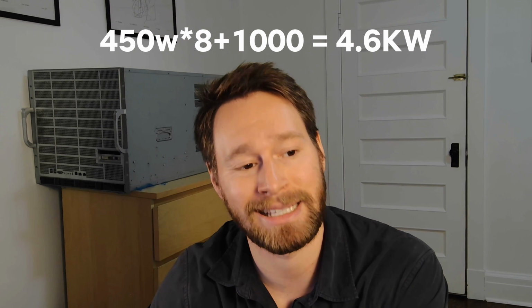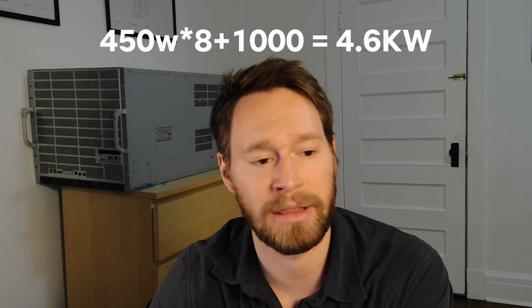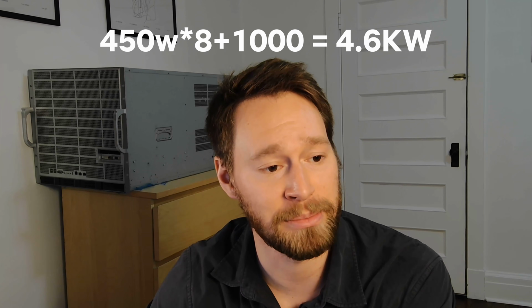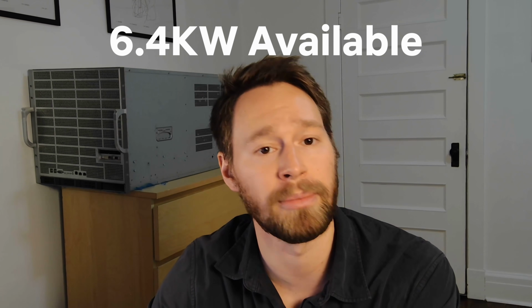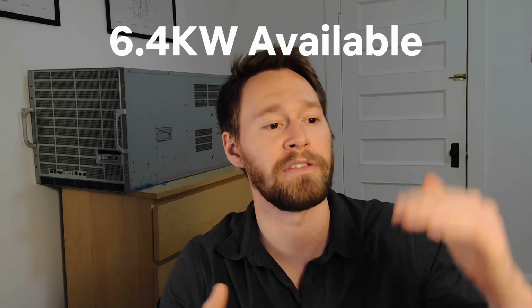For a 4090 server, the math is you need about 4.6 kilowatts to run it. I think that math was just TDP of the GPUs plus 1,000 watts. By having four 1600 watt PSUs, you're at 6.4 kilowatts available. That was a healthy enough margin that we were typically well below that 80% threshold, so if we lost a PSU, chances are we could continue operating on 3 PSUs with redundancy intact.